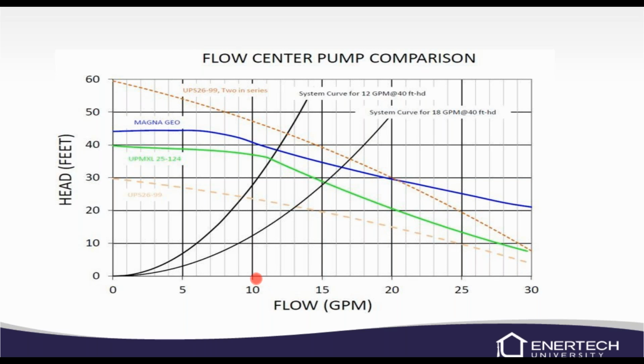And so normally we're going to be within the 10 to 15 GPM range. So it can handle 11, 12 GPM at a little under 40 feet of head. And at 15, we're running about 35 feet of head. So you should be good with this pump. If you've got to replace for some reason, you've already got a 32-140, the 25-124 should work for you just fine.